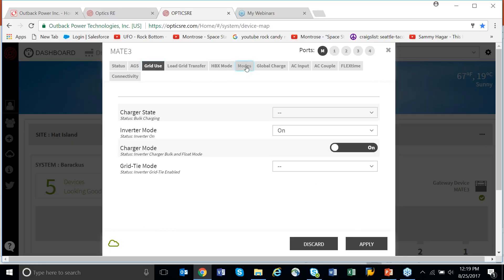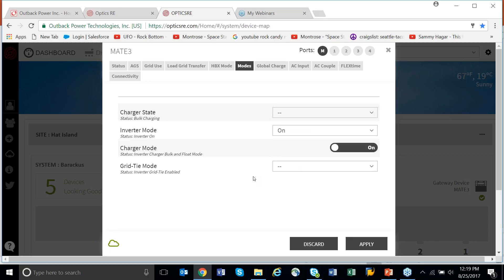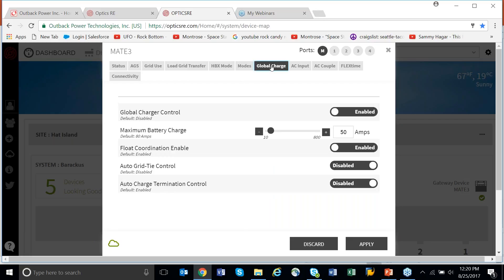Let's go to Modes. On the charger you could start or stop a bulk charge, start an EQ charge and stop one. Inverter mode: on, off, or search. Charger mode: on or off. Grid-Tie Mode: enable or disable. You can make these necessary adjustments from here. We've got global charge control — some of the advanced functions on the Mate now. You can enable global charging and limit the amount of current into your batteries should you need to.